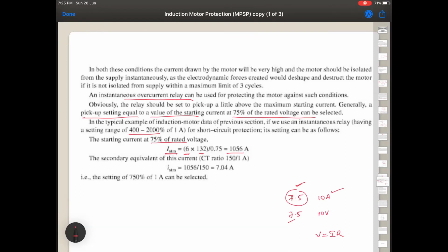We have got the starting current of an induction motor, and this is a primary current. The equivalent secondary current we get by dividing by 150, because the CT ratio is 150 by 1 ampere. So we get this, which is almost equal to 750% of 1 ampere. It means the relay setting you are setting in terms of percentage, and the rating of the relay is 1 ampere.